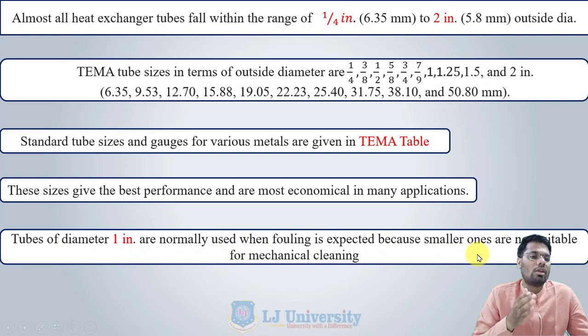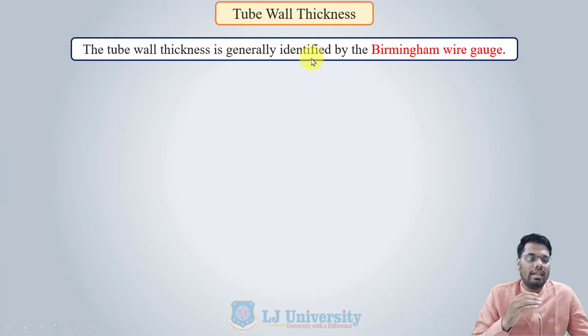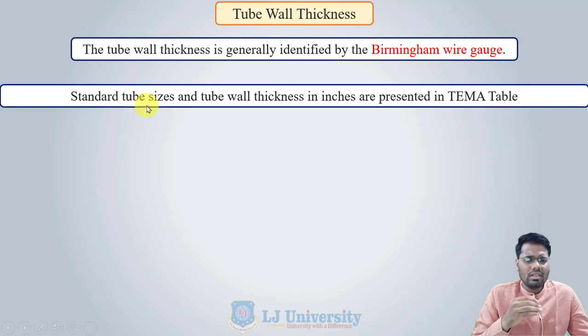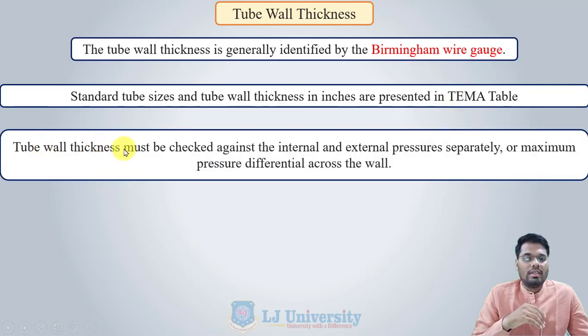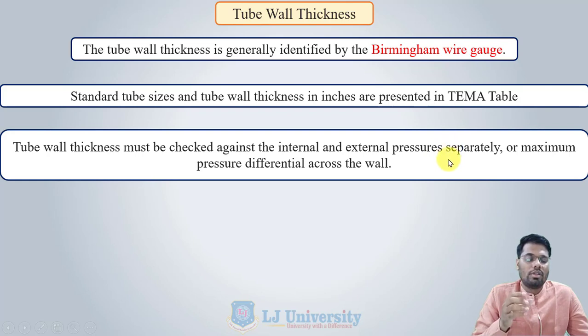Tubes of 1 inch diameter are normally used when fouling is expected because smaller ones are not suitable for mechanical cleaning. Tube wall thickness is generally identified by the Birmingham Wire Gauge (BWG). Standard tube sizes and wall thicknesses in inches are presented in TEMA tables. The tube wall thickness must be checked against both internal and external pressure separately, since the thickness is primarily responsible for withstanding the fluid pressure, and the maximum pressure differential across the wall governs the design.